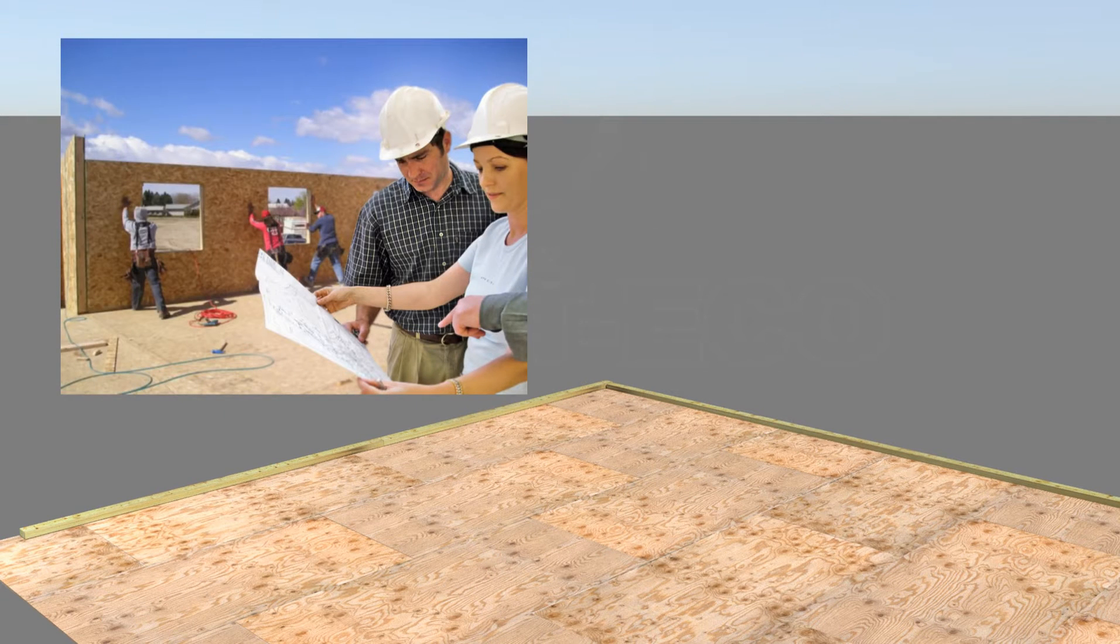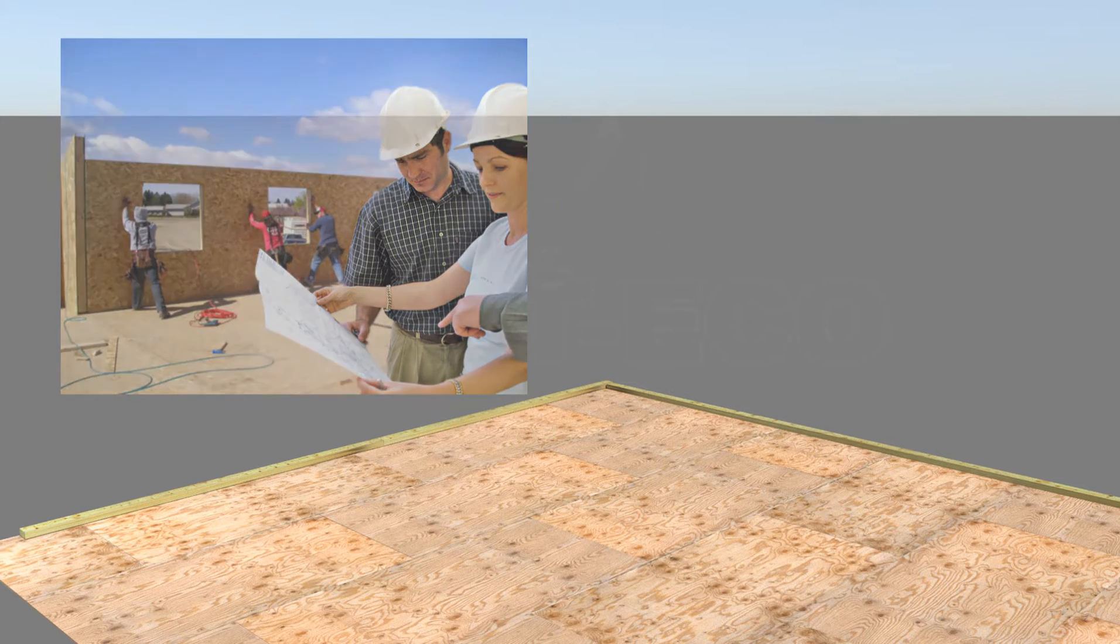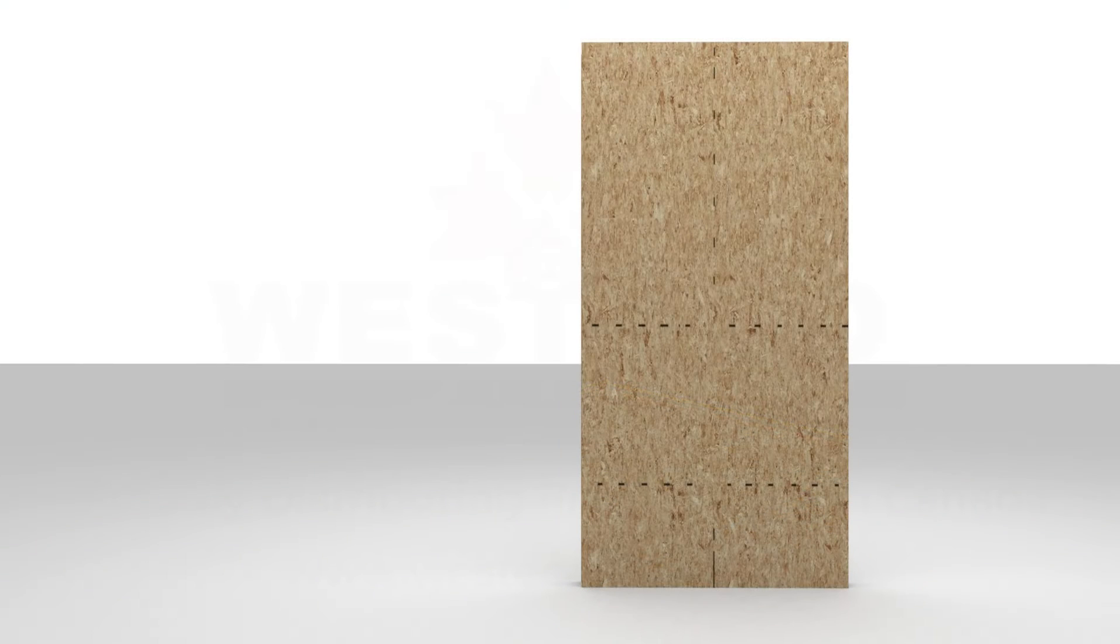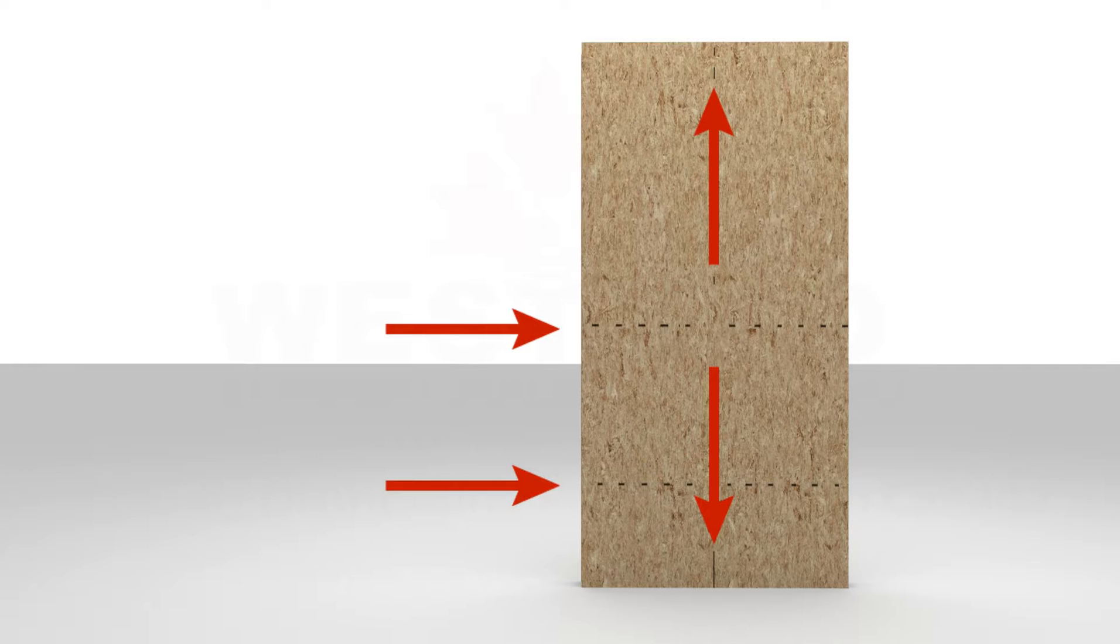Review the SIP layout drawing to confirm the locations of the vertical electrical chases factory cut into the cores of the SIPs. Take note of the factory cut electrical chase location markings on the face of the SIPs. On both the subfloor surface and the face of the installed bottom plate, mark the corresponding locations where the SIP vertical chases will occur.